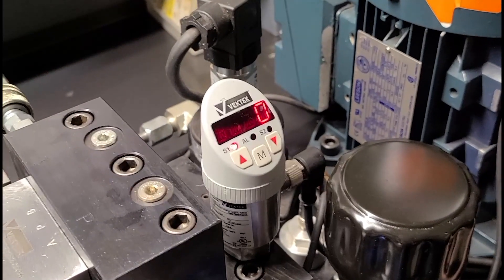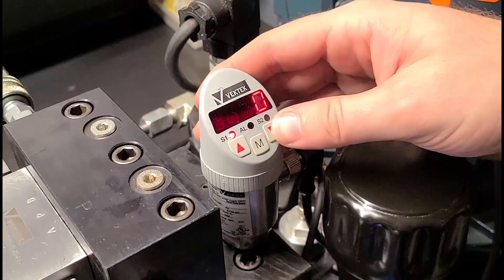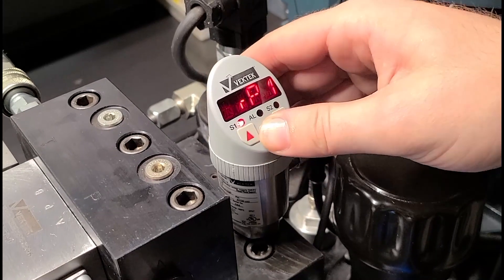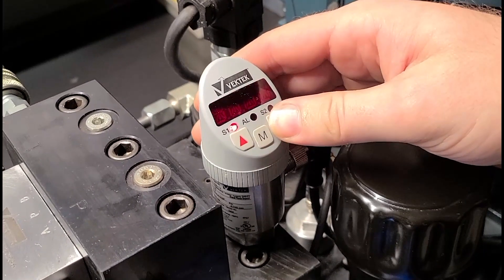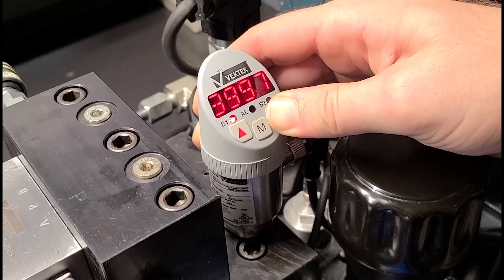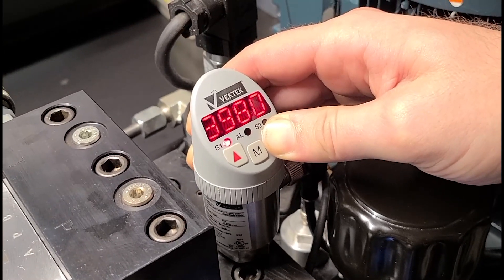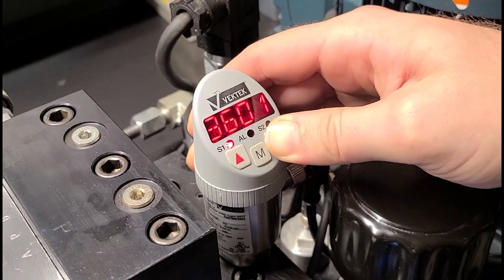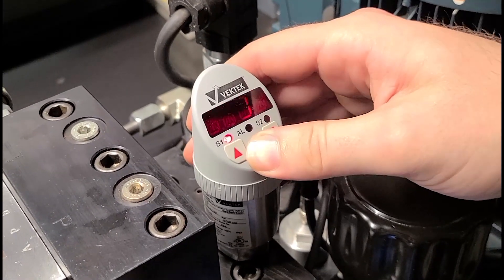To reduce the pressure on our Vektek Digital Pressure Switch, you'll have to adjust the reset pressure first. You can do so by clicking the Modify menu button. And we're going to take it down from 4,000 to 3,600 PSI. And then you'll have to click the Modify button again to set it.